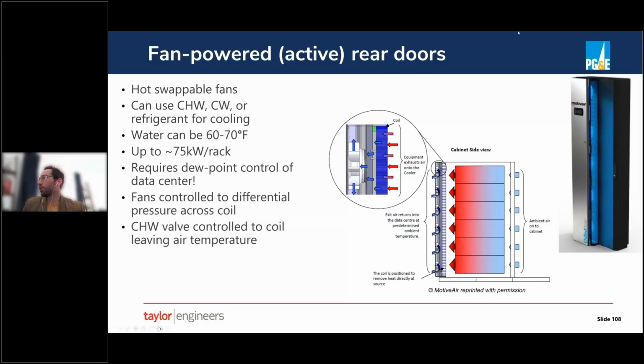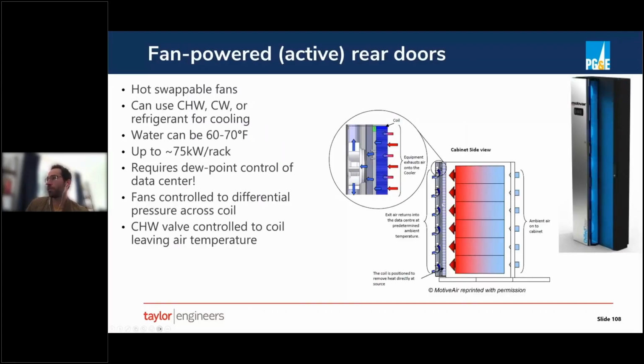An active rear door is different than a passive rear door because it has integral fans. So we're no longer relying on the fans within the server racks themselves to move air across the rear door. The way this is controlled is you'll have a differential pressure sensor across the rear door assembly. If you see where my cursor is here, you have a DP across this, and the fans will modulate to maintain that DP at effectively zero, right? Because what happens when the fans turn off? Well, if the fans are off, then the differential pressure between the servers and the coil starts to build up. And as the airflow across the servers increases, that DP builds up, and the PID loop responds by increasing the server fan speed to maintain effectively zero DP across this assembly, which means the door flow is matching the rack flow. And so these can go up to fairly high densities, here we know up to 75 kW per rack. No different than a passive rear door, you still require dew point control within the data center.